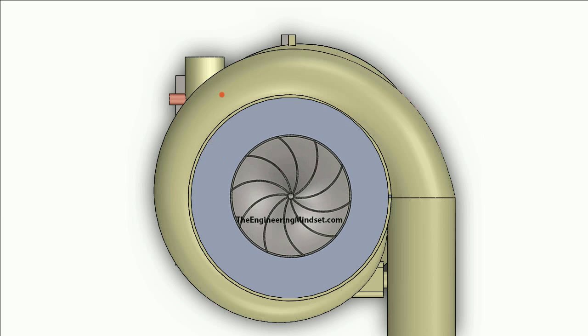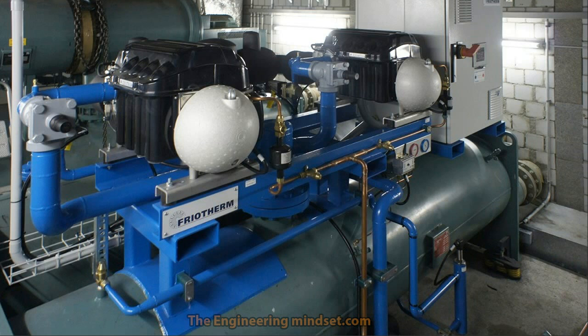This is a very common setup for a central plant in large buildings. A variation is the Turbocor compressor, which looks something like this — small units mounted on the top of the chillers, usually at least two of them. These work just like the centrifugal type but have two-stage compressors inside, very small ones. The refrigerant flows in through the front, passes through the two compressors, and exits down into the condenser. These usually have magnetic bearings and electronic motors inside, making them very efficient. They're going to become a lot more common as older technology is replaced by this more efficient version.